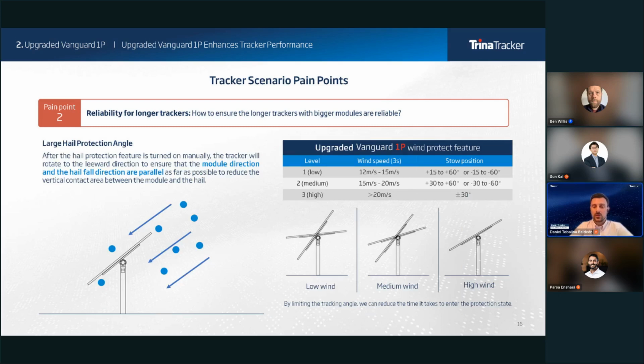By doing this wind tunnel test, we could define the optimal stow strategy, in this case 30 degrees facing the wind. In addition, we have defined 2 pre-alarms depending on the wind speed. With these pre-alarms, we will reduce the tracking angle, and by doing this we are maximizing the energy production while reducing the time the tracker takes to go to stow position.